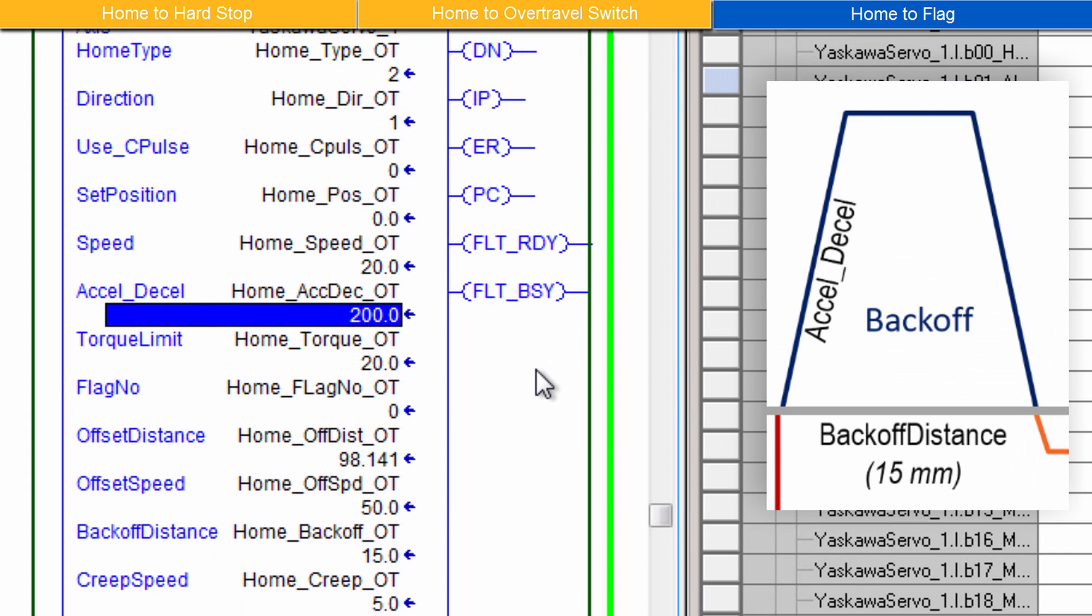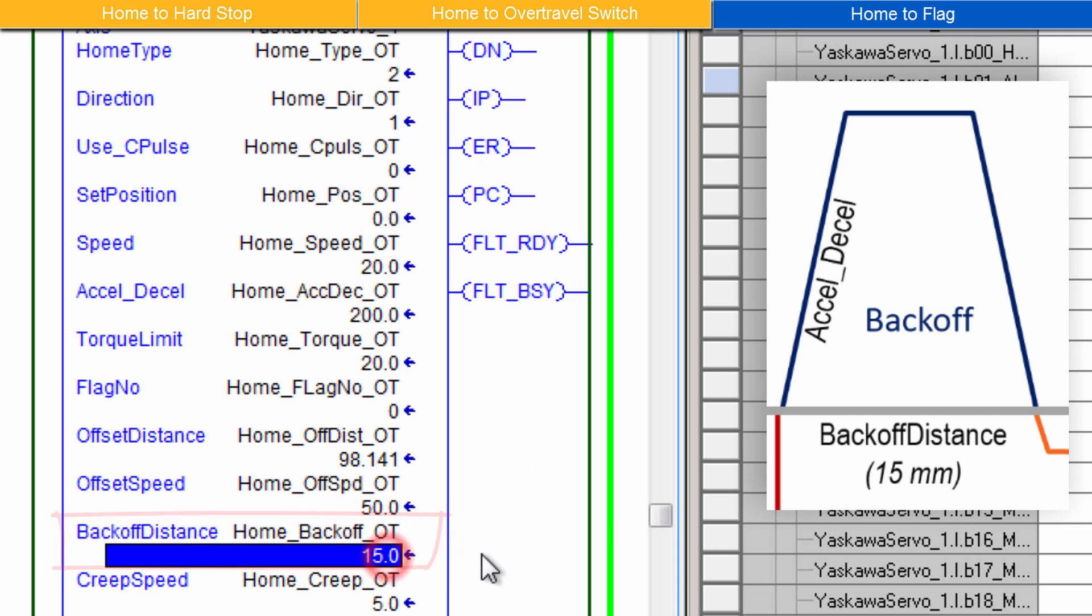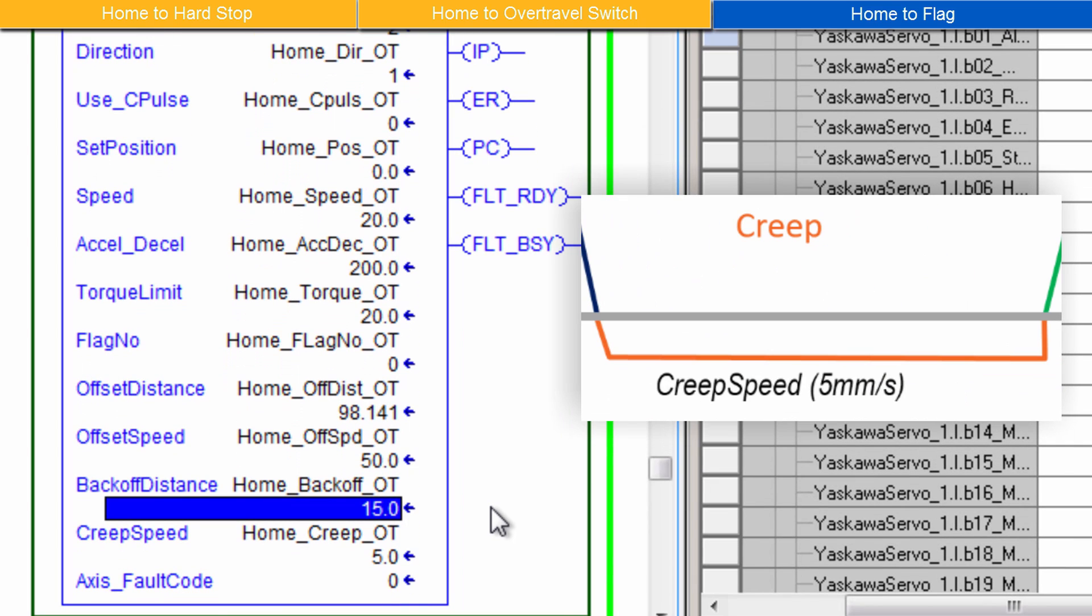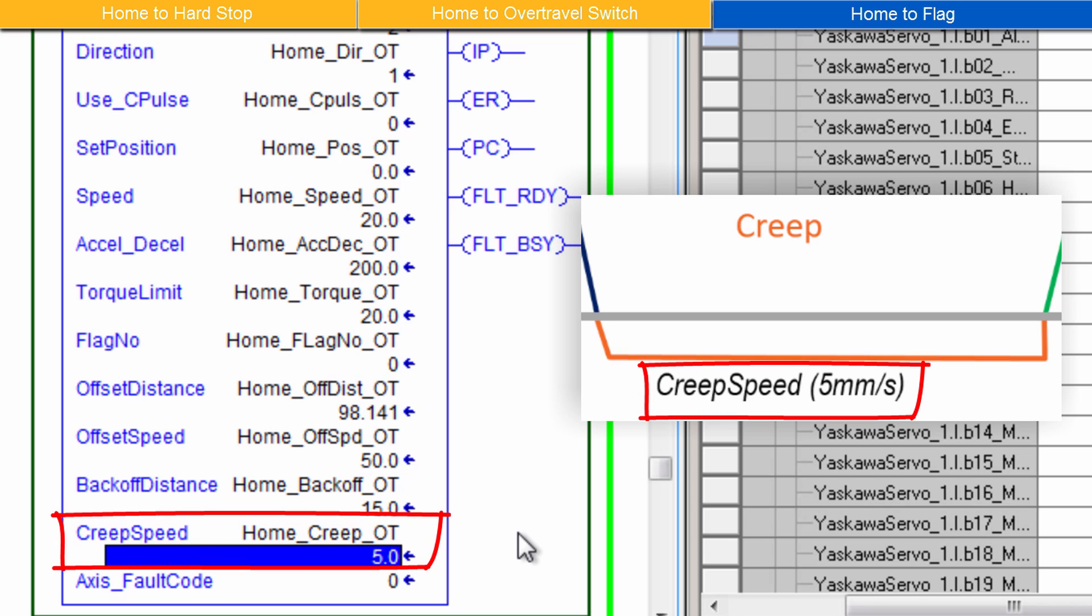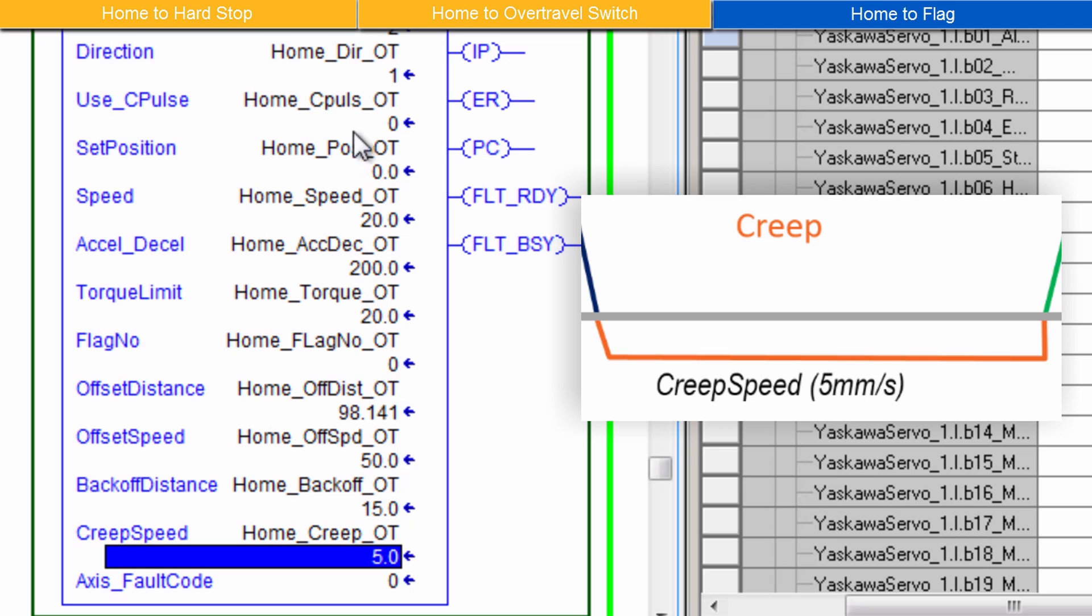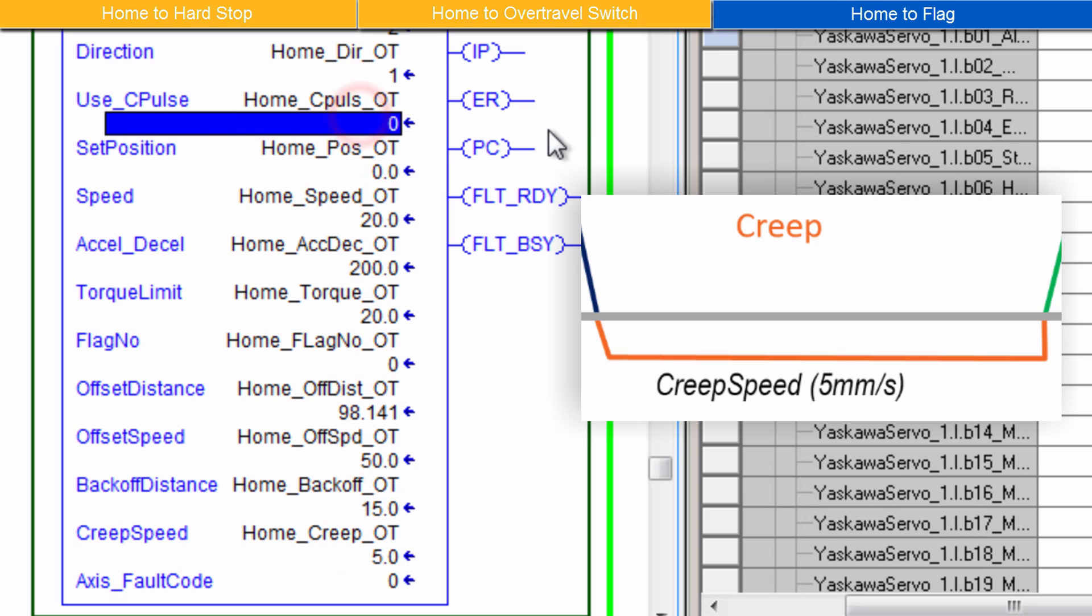Next is the Back Off Move. This is a short back off distance before finding that sensor again. I'll use 15 millimeters. Now the Creep Move. Set a Creep Speed to move slowly toward the sensor until it stops. I'll use 5 millimeters per second. Instead of creeping toward the sensor, use C-Pulse. C-Pulse could be enabled to creep slowly away from the sensor stopping at the encoder's C-Pulse. I'll leave this feature disabled in this example.